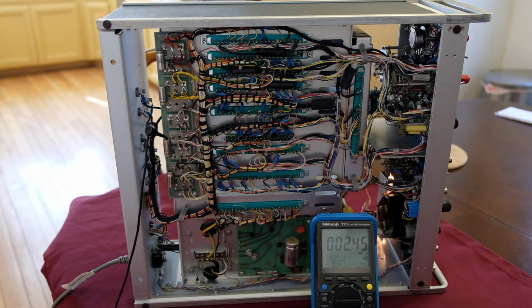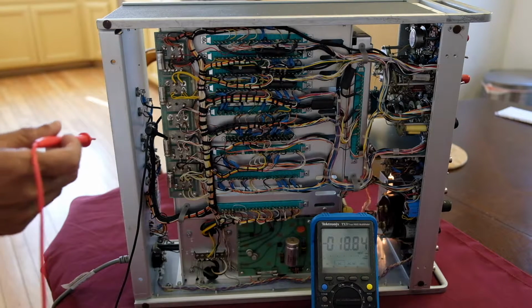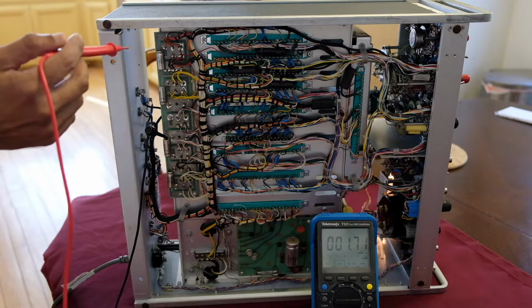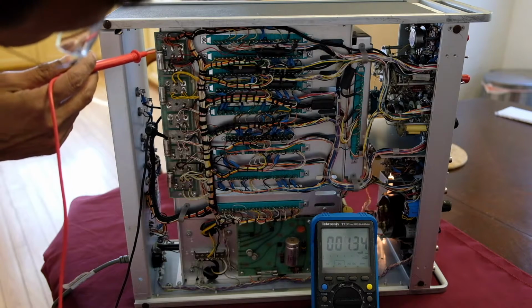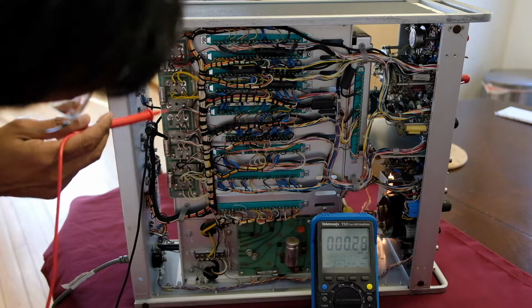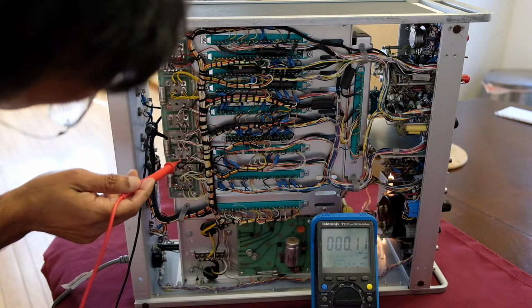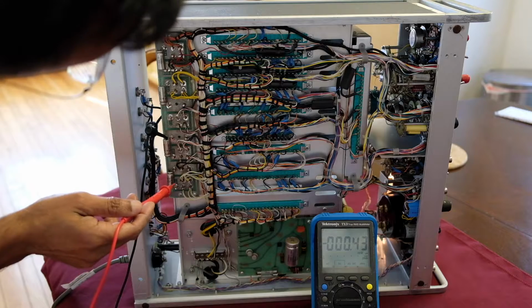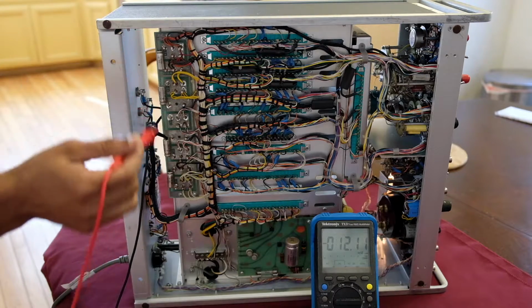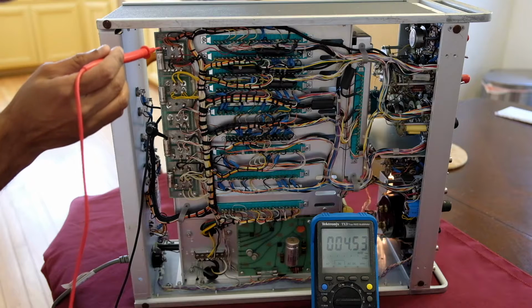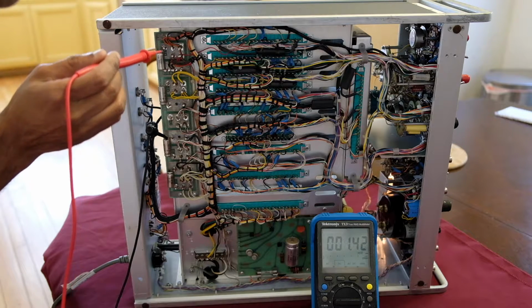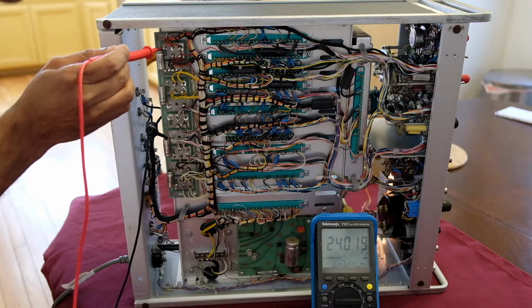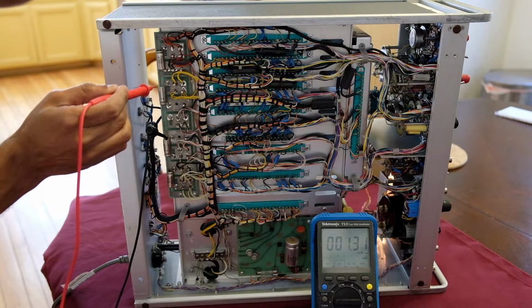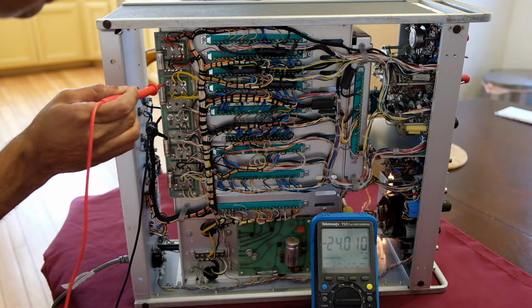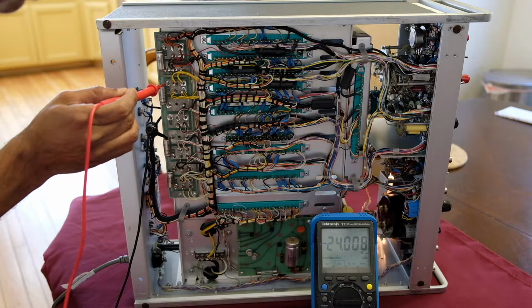Okay, now we're going to do some measurements on the power supplies. There are 5 power supplies here, low voltage DC supplies. The first one is a plus 24, the next one is minus 24, the third one is a plus 4.5, there's a plus 12 and a minus 12. So, connect ground, which is common to all the supplies from what I can see. If I measure the main power supply pins, that should give you a reading. So this is 24 volts, and it's reading 24.018. Second one is a minus 24 volt, it's reading minus 24.008.